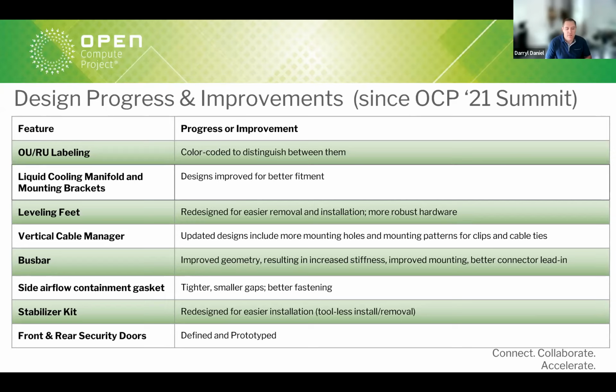For the side airflow containment gaskets, we've made some changes: tighter, smaller gaps to prevent any additional airflow bypass around the rack. We've also changed how those are mounted and fastened to the rack frame itself, still a toolless design for mounting those.